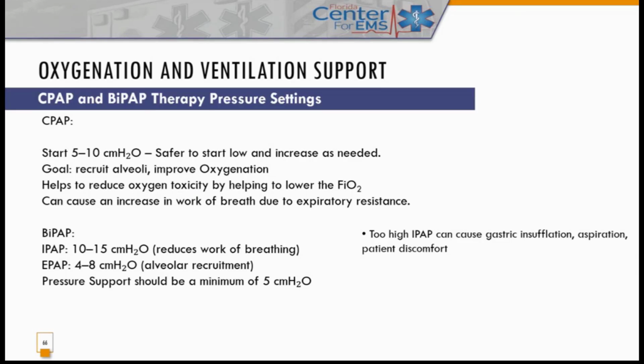Too high of an IPAP can cause gastric insufflation, obviously creating possible vomiting and aspiration, and it's also uncomfortable for the patient if we have too high of a pressure. Too low causes inadequate ventilation. The CO2, or end-tidal CO2, is going to go up. So it's not one of these things, set it and leave it. It's set it, monitor it, and adjust as needed. Too often, I've talked to people who want a standard setup. Tell me what to put it on, and they put it on that, and they never come back to make the change. It just doesn't work that way.